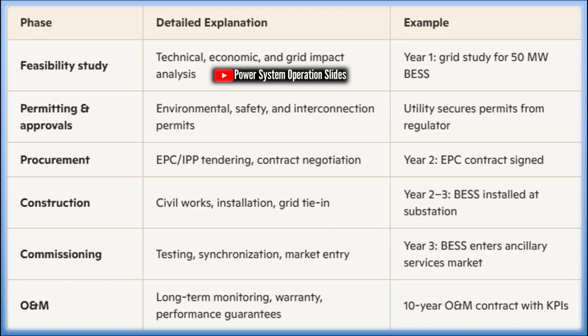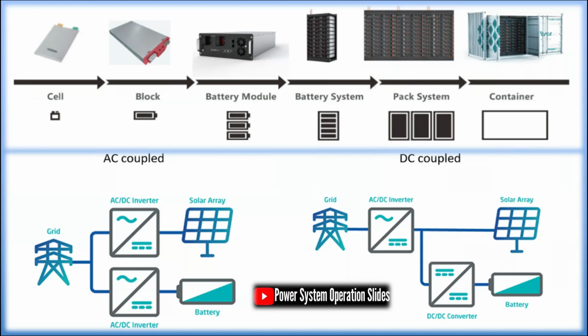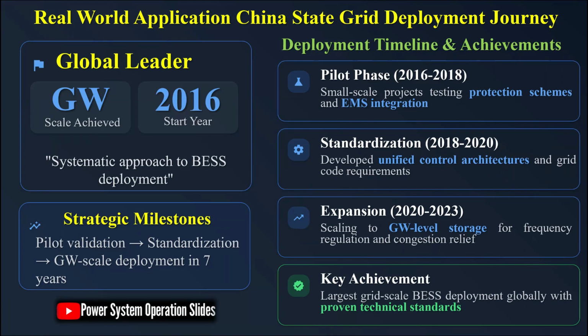The fifth question addresses procurement models for BESS, comparing centralized utility ownership with public-private partnership, PPP, or independent power producer, IPP, models. The choice of procurement model has significant engineering implications because it directly impacts asset control, dispatch authority, maintenance responsibility, and performance guarantees. Centralized utility ownership provides full operational control and enables tight integration with the utility's EMS systems. This integration facilitates coordination with other grid assets and reduces the risk of operational conflicts. Under centralized ownership, the utility assumes performance risk, degradation risk, and maintenance responsibility, providing complete control over asset operation but also bearing full responsibility for asset performance.